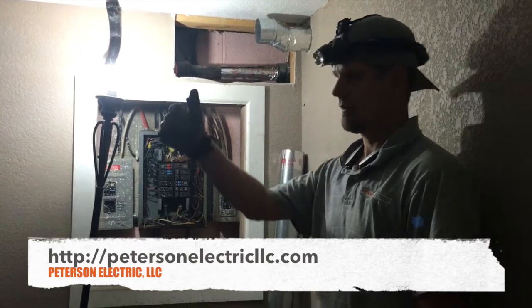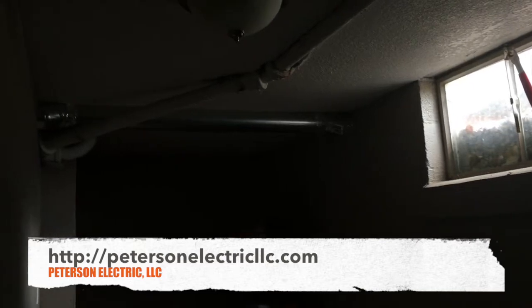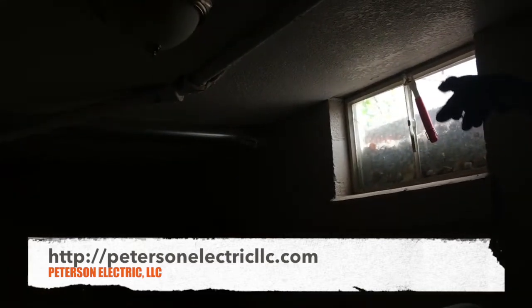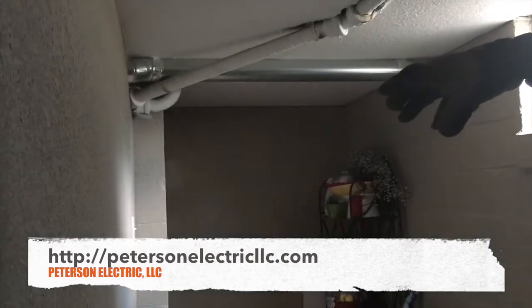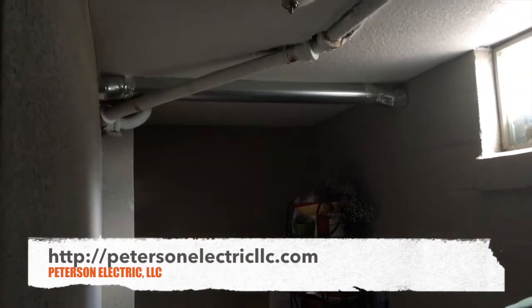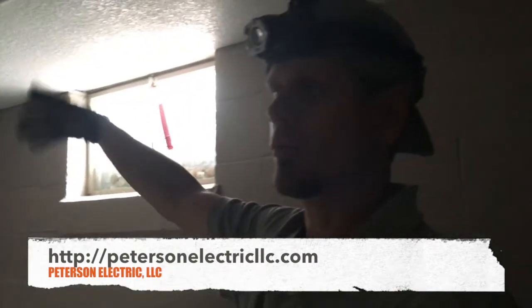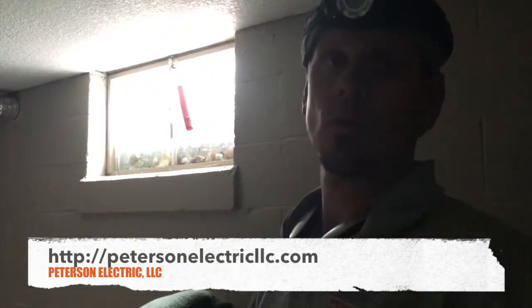But yeah, we have to cut the ceiling out in here to get the water grounded, and then that ceiling over there has to be cut out to get right up where, through this window, the service entrance comes in. And then this will now become a sub feed, and the outside will have to have a disconnect by code, by city standard, with a new meter and a new riser, and the power comes in overhead.